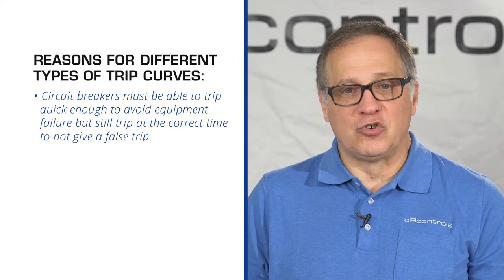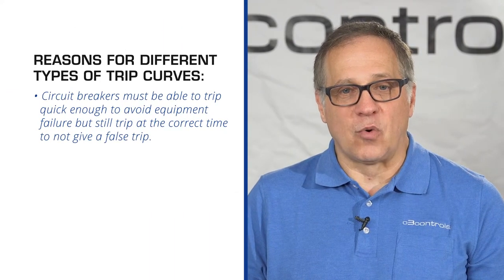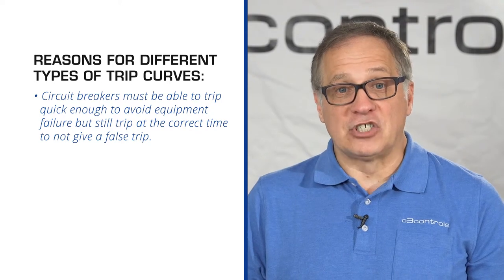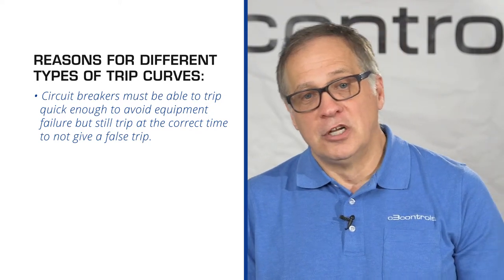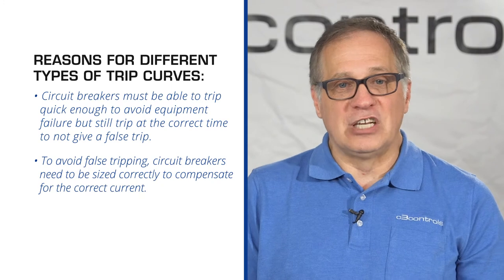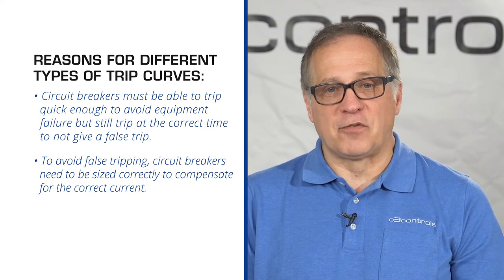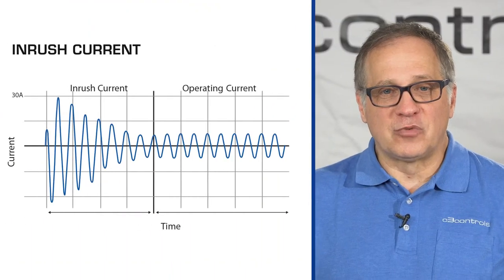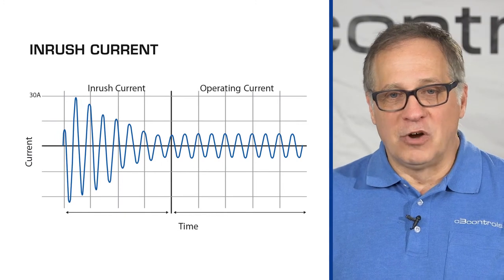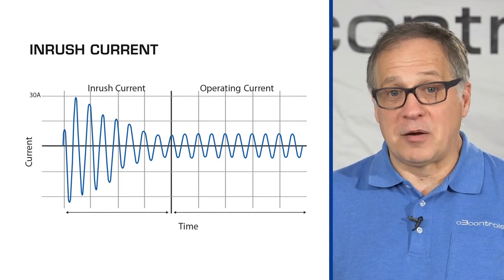We need different types of trip curves because circuit breakers must be able to trip quickly enough to avoid equipment or wiring failure, but not so fast as to give a false or nuisance trip. To avoid nuisance trips, circuit breakers need to be sized appropriately to compensate for inrush current. NEMA defines instantaneous peak inrush as the momentary current transient that occurs immediately within half of an AC cycle after contact closure. Inrush current is what causes the lights to dim in your house when a motor such as that on a clothes dryer or vacuum cleaner starts up.